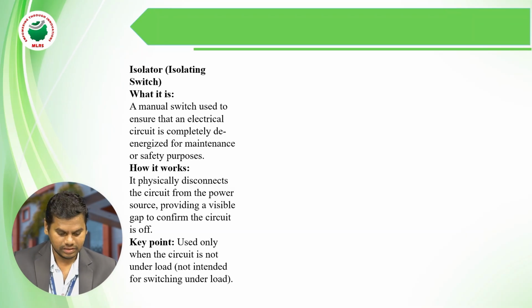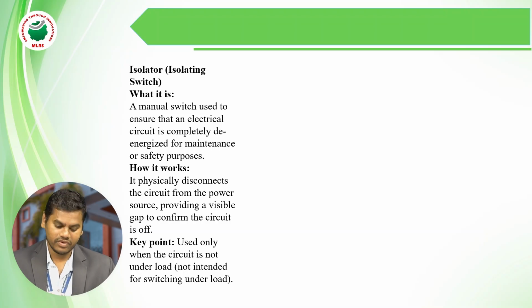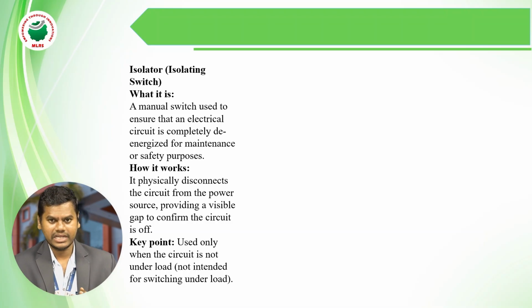Next, the isolator, which is an isolating switch. What is an isolator, how does it work, and what is the key point involved? First, the definition: an isolator is a manual switch used to ensure that an electrical circuit is completely de-energized for maintenance or safety purposes. It works by physically disconnecting the circuit from the power source, providing a visible gap that confirms the circuit is off. The key point is that it is used only when the circuit is not under load, not intended for switching under load.